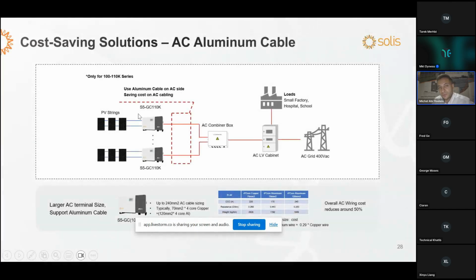Another feature is all our inverter can support on the AC side the aluminum cables. Bigger cross-sectional cables are supported with our inverter. So for the same capacity, instead of using a copper cable with let's say 70 millimeter cross section, we can use maybe 120 millimeter of aluminum, which can give the same performance, but 30% or up to 50% cost saving.